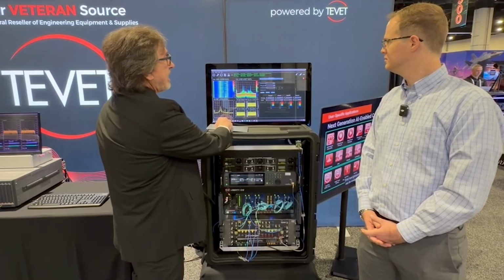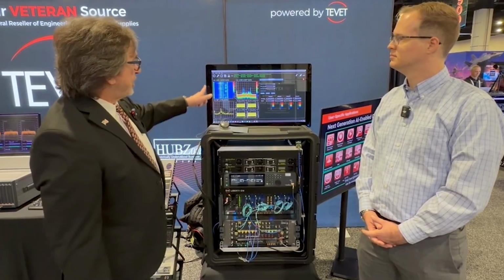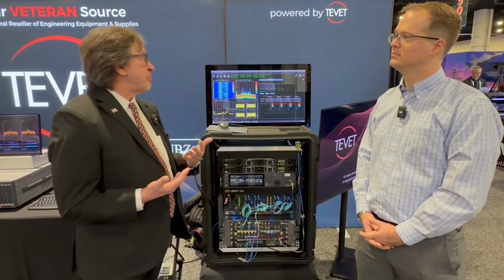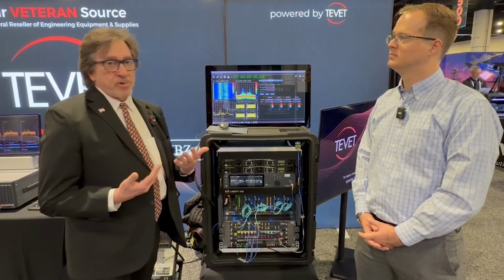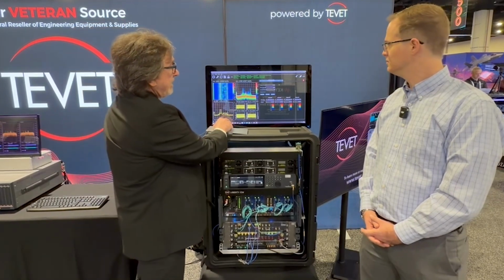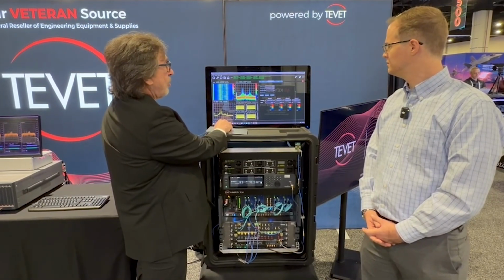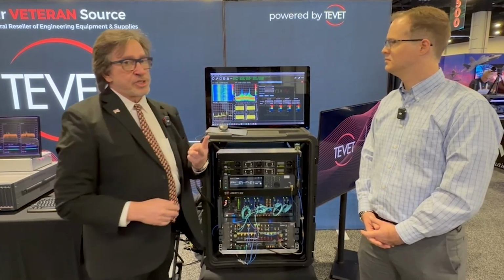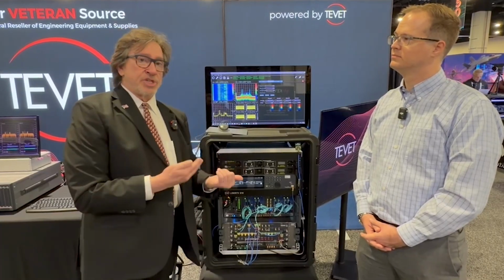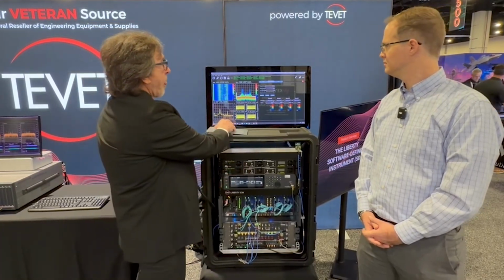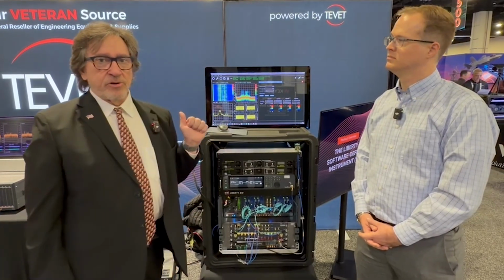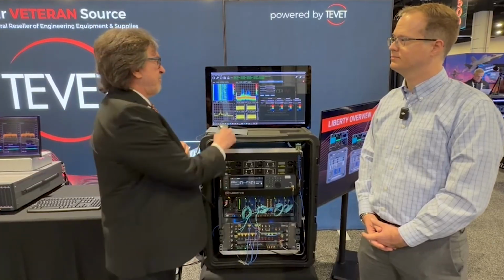If I come over, I can also control the spectrogram, which is in the upper left. I can control its sweep period and the number of frames that are displayed. I could also select this frame that allows you to come in. In addition to that, I can control the type of detector that you use in the system. You have 2 choices: interval peak and interval average. Depending on what your application is, you would choose one versus the other. In addition, I can control the color schemes of the spectrogram, and that's a user preference.